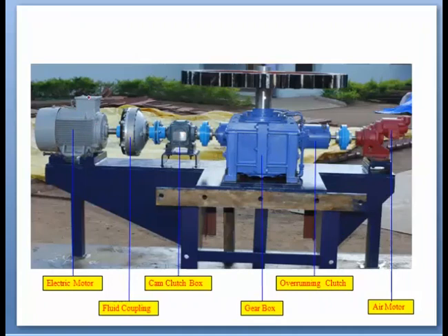Once this electric motor fails because of a failure in supply, we have to keep the air preheater rotating. In that case, this air motor will be used. The APH is required to be started before starting the boiler, and also to be kept in rotation for some time after stopping the boiler to avoid uneven expansion and contraction resulting in warping and cracking of the rotor.